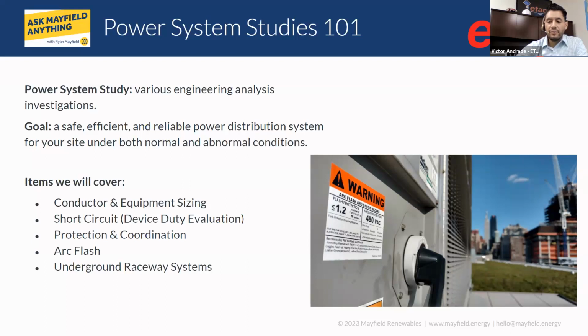So everybody wants to operate a system that will outlive the design life, and more importantly, to be safe. So power system studies help us get to that point, operate a safe, reliable power system. If, for example, there is a fault somewhere on a low voltage location, we isolate the fault there. So a power system study helps us add reliability to the power distribution system. So it's definitely more than just a requirement. As we look at power system studies more in the safety aspect, I think we're able to do a better job and better justify that it's important for human safety and also for the safety of the equipment.